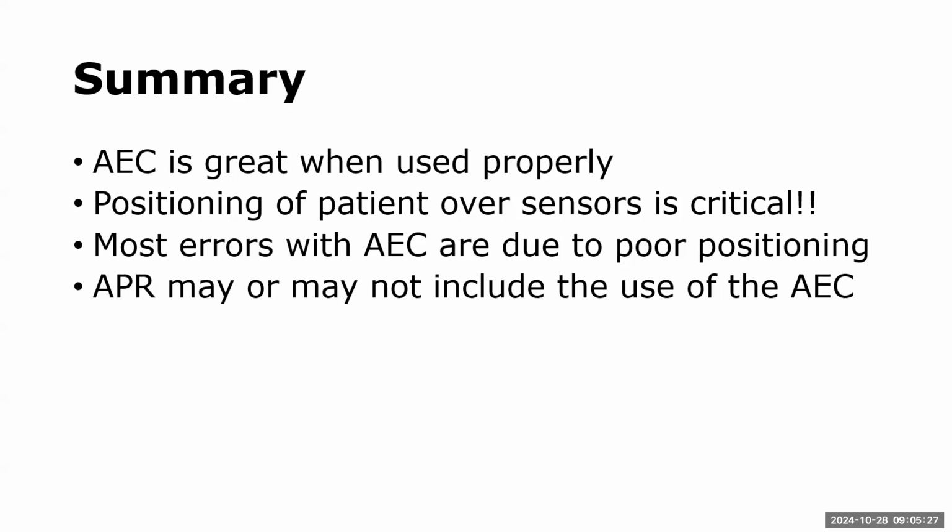So AEC is great when used properly. Positioning of the patient over the sensors is critical. Most errors that occur with AEC are our fault due to positioning. And APR may or may not include the use of AEC. So AEC can be programmed into the APR.